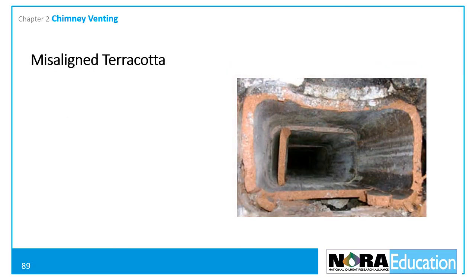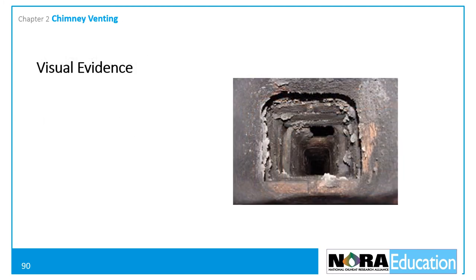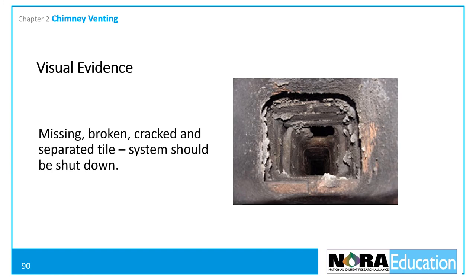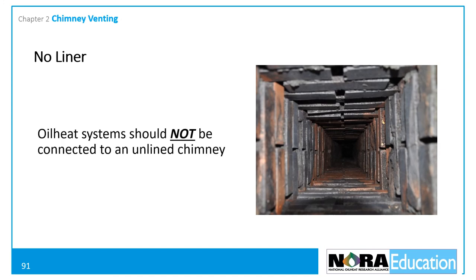Misaligned terracotta tiles at the joint, as well as missing, broken, cracked, or flaking tiles are additional warning signs. Visual evidence of severe damage — including missing, broken, cracked, and separated tiles — warrants shutting down the system. No liner installed: oil heat systems should not be connected to a chimney without a liner.